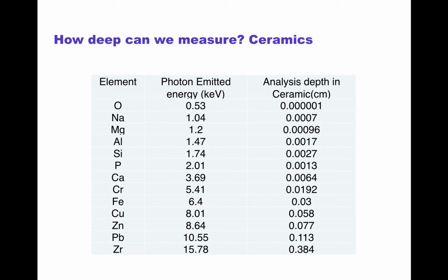Typically, X-ray quantification follows one of two paths: to have every sample be uniformly thin, or every sample be uniformly thick. Laboratory and benchtop systems typically require sample preparation in the form of fused beads. This does two things. It creates a matrix of the same type, which means measurement depth is the same, and it makes all samples the same thickness, meaning they're appropriate to that quantification method.